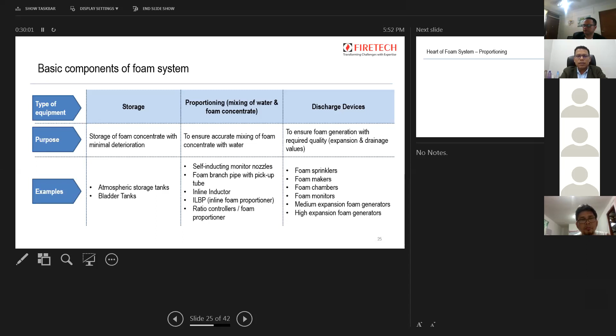Now proportioning. This is one of the most important components of the foam system. Proportioning means mixing the accurate quantity of the foam concentrate into water. And this is the heart of the system, because unless you have the correct amount of foam mixed in water, there is no possibility of producing the correct quality of foam which can extinguish the fire. Some examples of proportioning devices are self-inducting monitor nozzles, foam branch pipe with pickup tube, inline inductor, inline foam proportioners, and ratio controllers. And the last are the discharge devices, which ensure that the foam is generated with the required quality, as I said earlier, that is expansion and drainage. Examples are foam sprinklers, foam makers, foam chambers, foam monitors, medium expansion foam generators, and high expansion foam generators. So every foam system has these three components: storage, proportioning, and discharge devices.